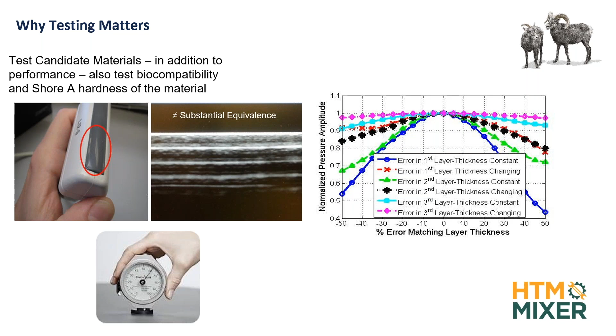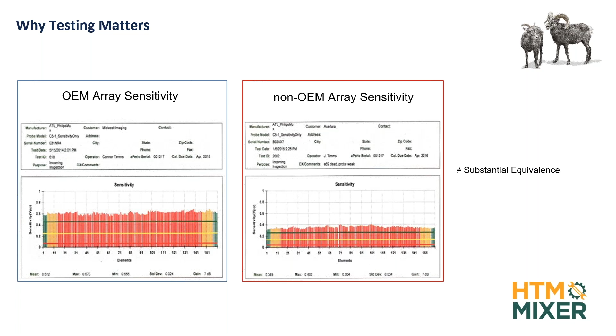Here's an array. This is a report from our system called First Call, and here's the sensitivity of an OEM array. Here was the sensitivity of an array that came from China, and the hospital complained that the depth of penetration wasn't there. Again, it does not equal substantial equivalence to the OEM. It shouldn't be used, or they should have filed a 510(k). They don't even know that they're supposed to do that, in our experience.